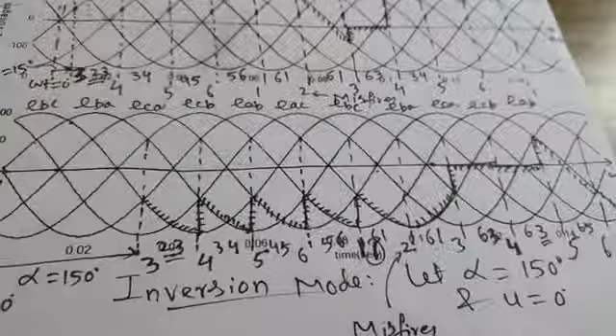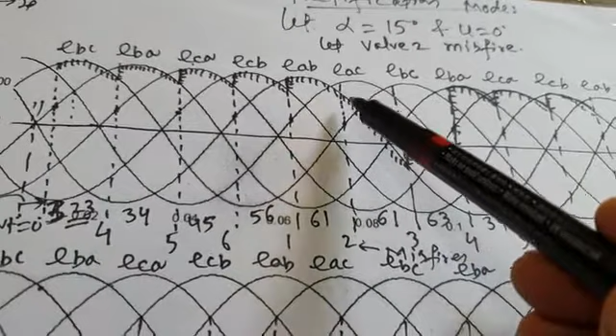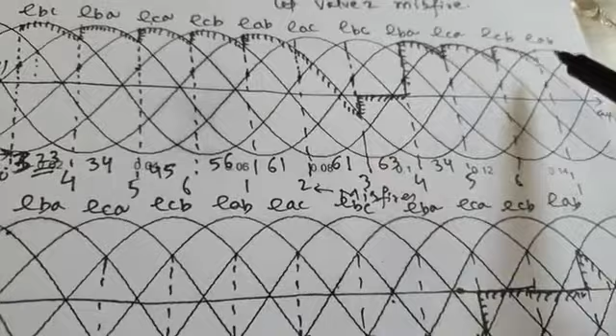So this is the load voltage waveform for the inversion mode of operation with what mal-operation? Misfire. We have assumed valve 2 misfires. So these are the load voltage waveforms for the rectification mode of operation and for the inversion mode of operation with misfire. Now, if you compare the two voltage waveforms, you can see that as soon as the misfire occurs in rectification mode, your load voltage, earlier following this pattern, stops following it. It follows this pattern, then it becomes 0 also, and then it resumes.